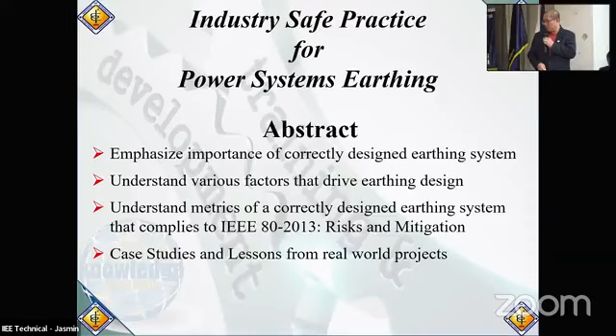So the importance of correct earthing design is to establish, as a design basis, safe limits of potential differences in a power system under fault conditions between points that can be contacted by the human body. Before I proceed, PEC versus IEEE 80.